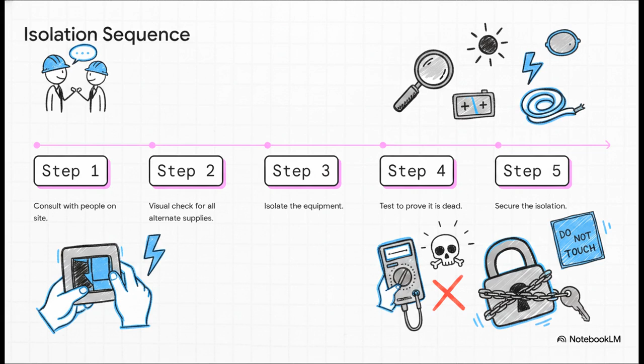Section 4. Foolproof isolation, the core procedure. Let's see how this builds. Here is the critical chronological sequence for cutting off all power sources. And yes, that includes backup batteries and solar. Step 1, consult with the people on site. Step 2, do a thorough visual check for all alternate supplies. Step 3, actually isolate the equipment. Step 4, test to prove it's dead. And Step 5, secure the isolation so nobody can undo it.